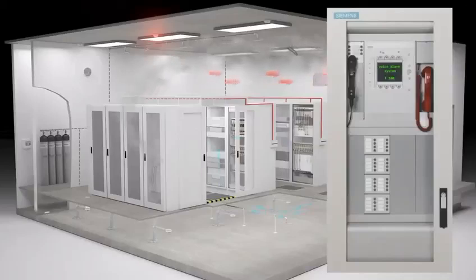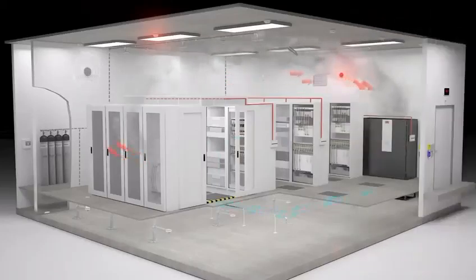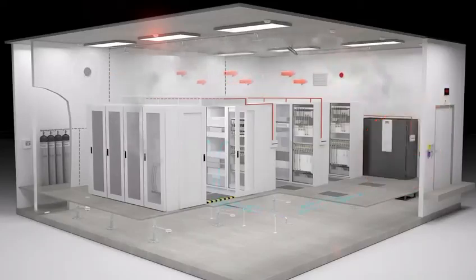The main alarm is transmitted to the fire department. The extinguishing process is activated and a delay time of 30 seconds is initiated. All openings in the flooding zone must be closed. People should leave the room.